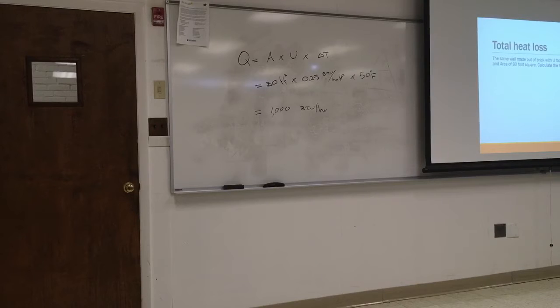We'll do something similar for the other type of heat loss. What are the two major heat losses in a house? Windows. What are they called? There are two things. Transmission, that's transmission. And the second type is what? Infiltration. Thank you. So this is for transmission. I will do one for infiltration. What is infiltration? Air exchange, air leak. Whatever terminology you find easier to understand this.